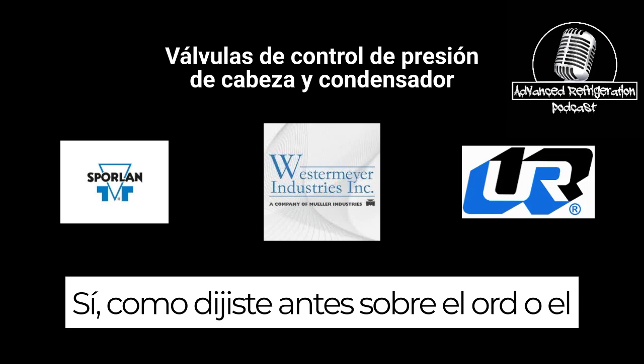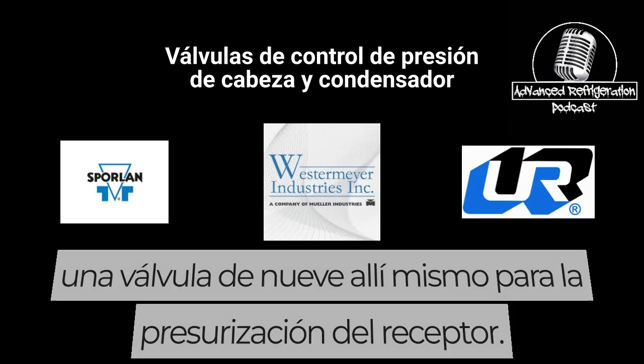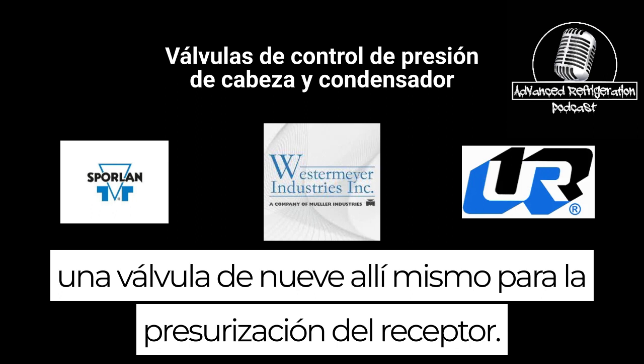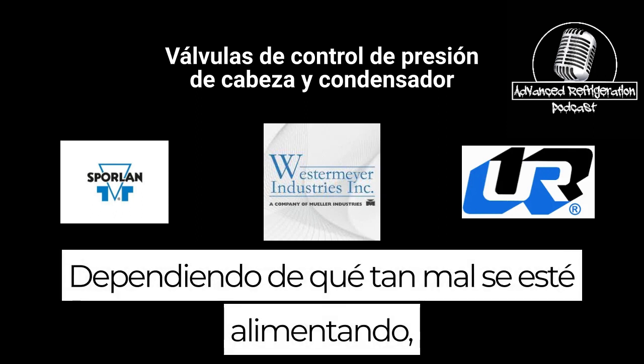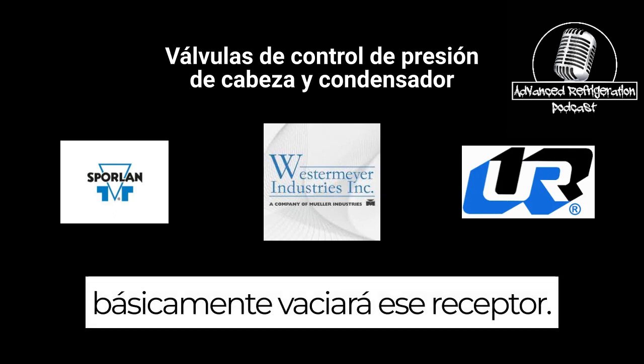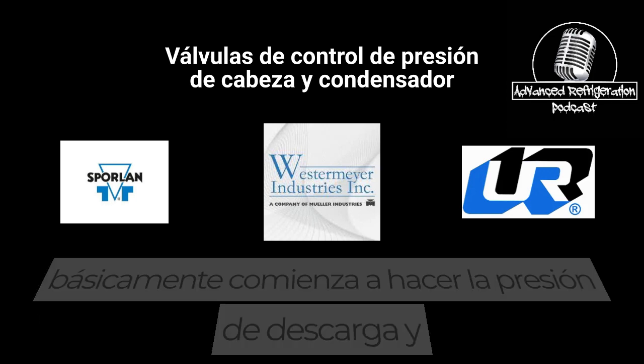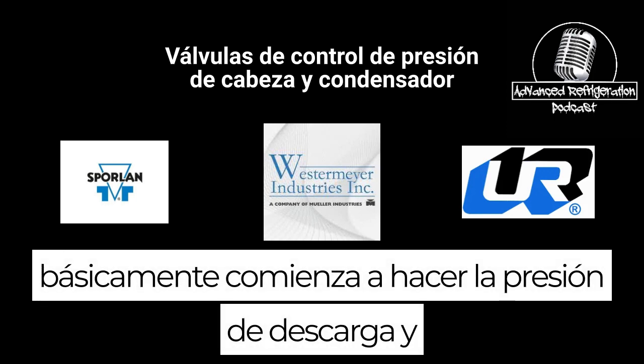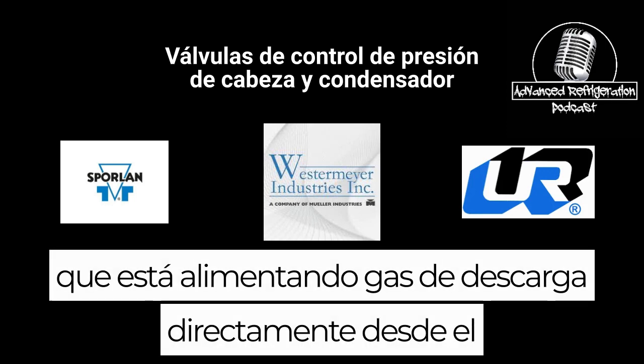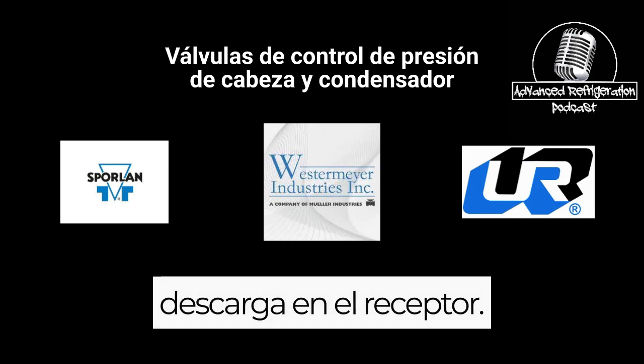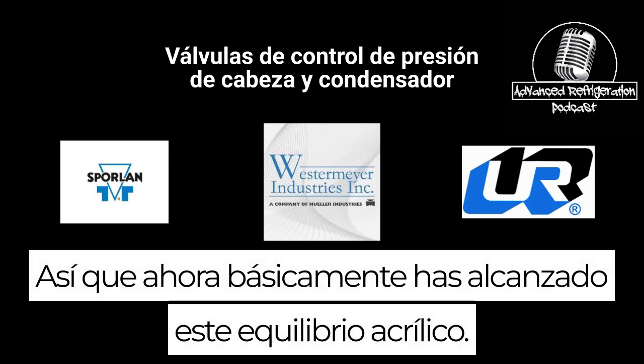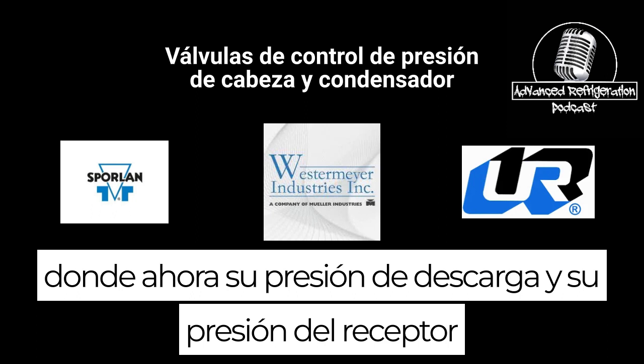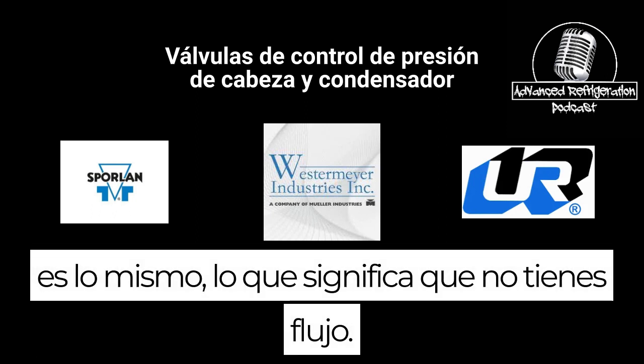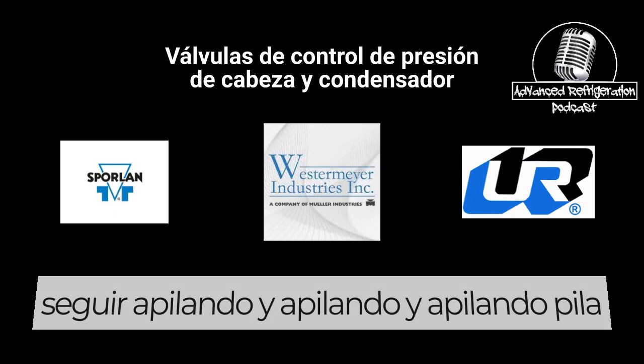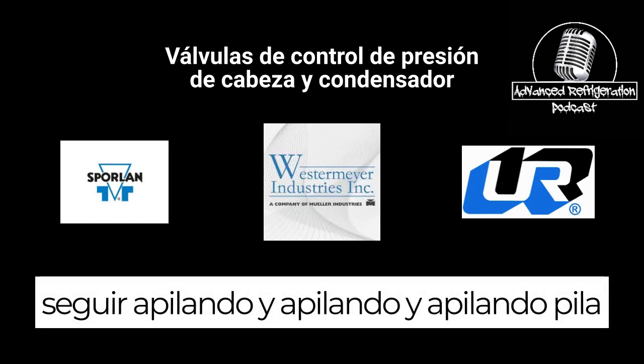Like you said before about the ORD or the A9 valve for the receiver pressurization, when that does feed, if it feeds when it's not supposed to, depending on how bad it's feeding, it will basically empty that receiver. The reason it'll empty the receiver is that you have to remember it's feeding discharge gas directly from the discharge into the receiver. So now you've reached an equilibrium where your discharge pressure and your receiver pressure are the same, which means you have no flow. So that refrigerant is just going to keep stacking and stacking into the condenser.